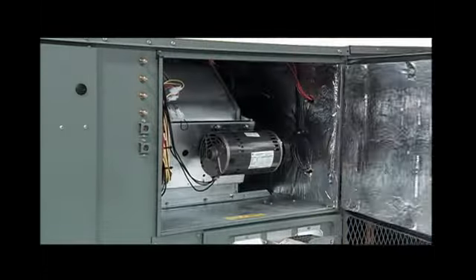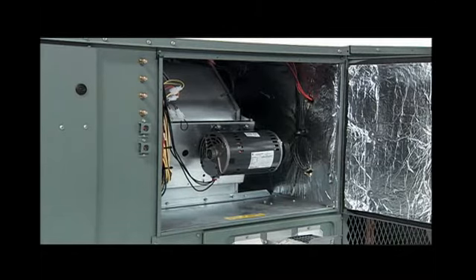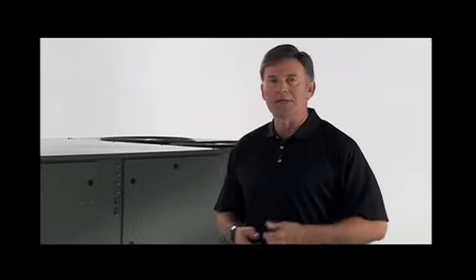To the right of the electrical and filter compartment are the externally mounted gauge ports, which are permanently identified by embossed wording that clearly identifies the compressor circuit, high pressure connection, and low pressure connection. With the gauge ports mounted externally, an accurate diagnostic of system operation can be performed quickly and easily. Brass caps on the Schrader fittings assure that the gauge ports are leak-proof.